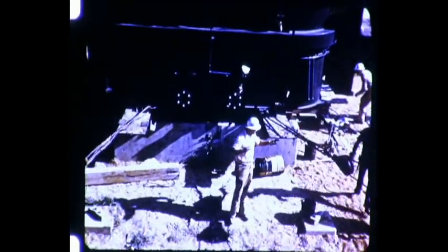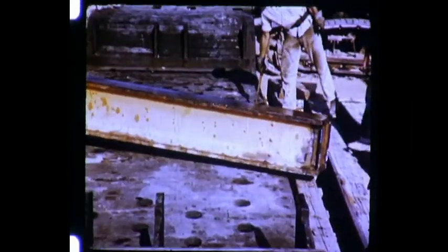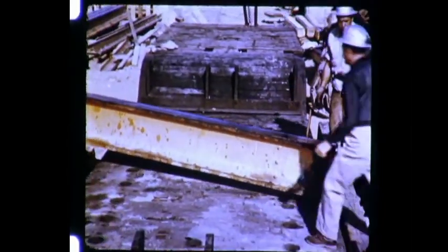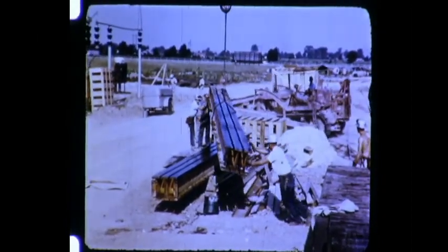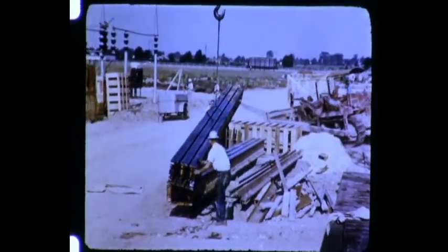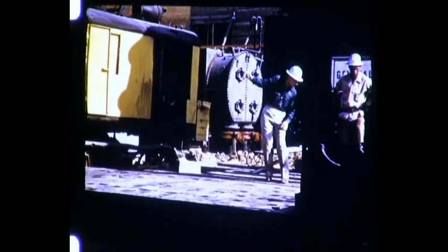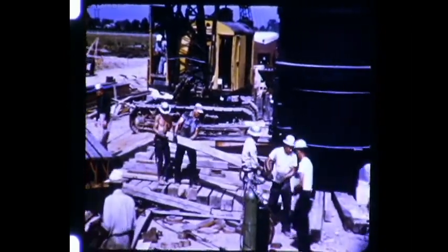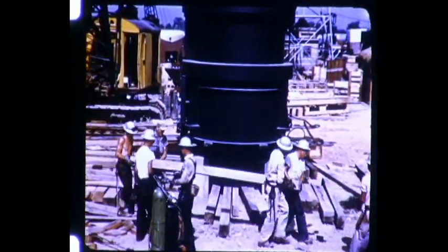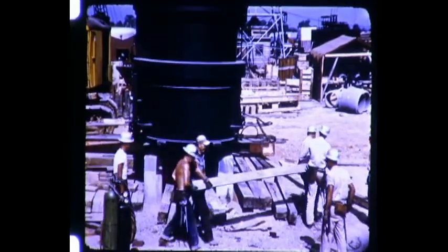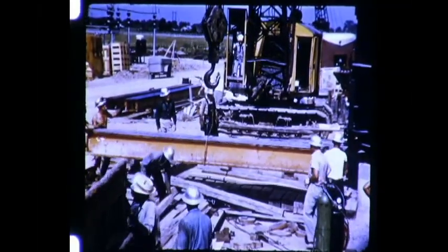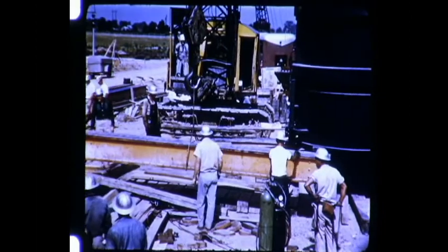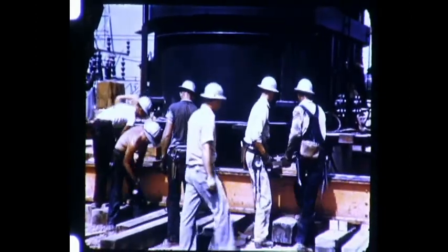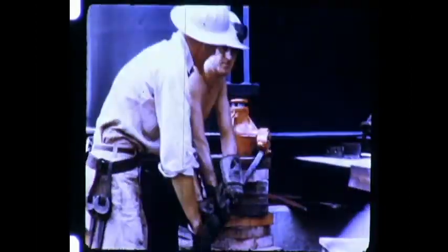As the big move ends, cables are loosened, and with the transformer off the car, the large skid beams can be removed. And now the car can be released to the railroad without delay. Before the transformer is lowered and adjusted into final position, cribbing is built at both ends of the footings. This will enable the crew to jack the unit up just enough to free the skid plates and beams, and then lower the unit to its permanent location.